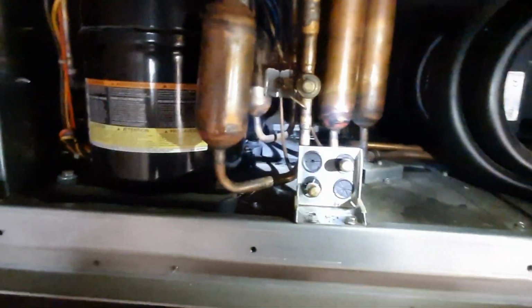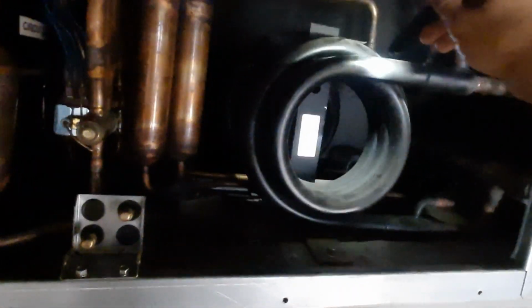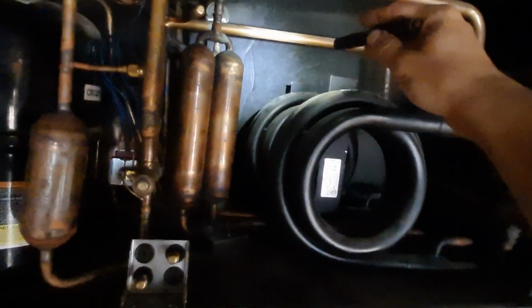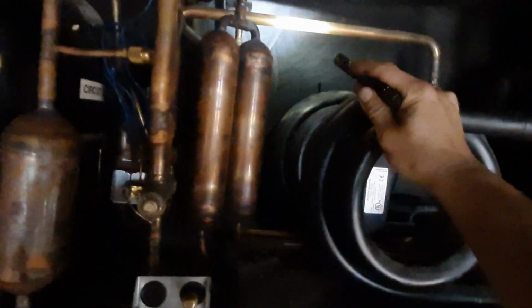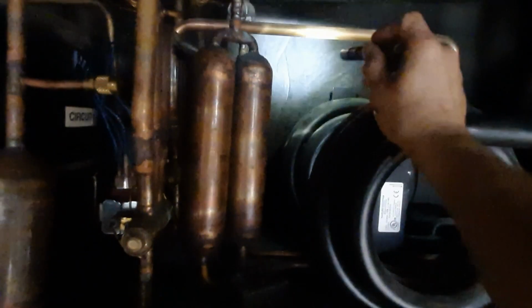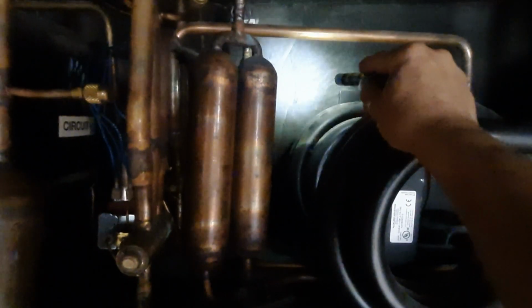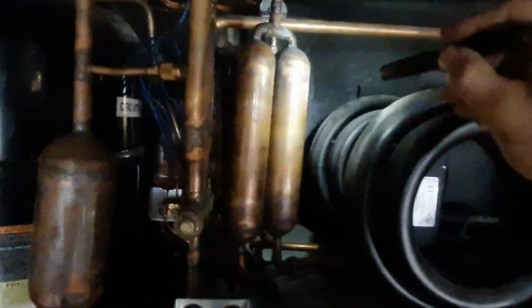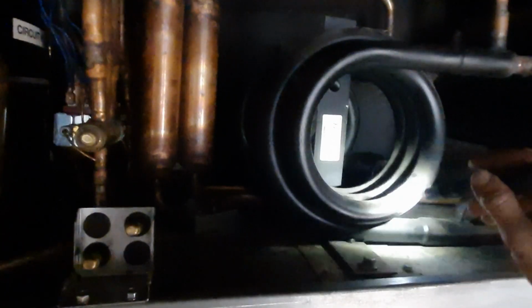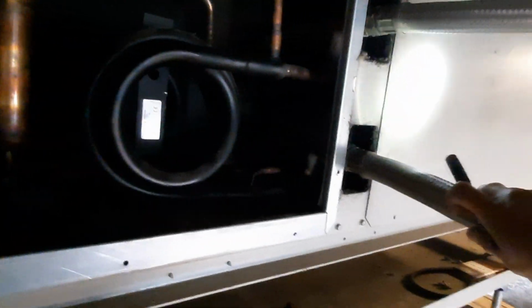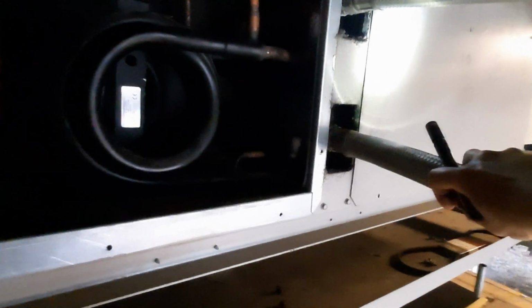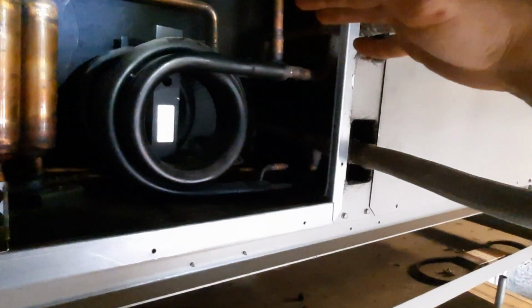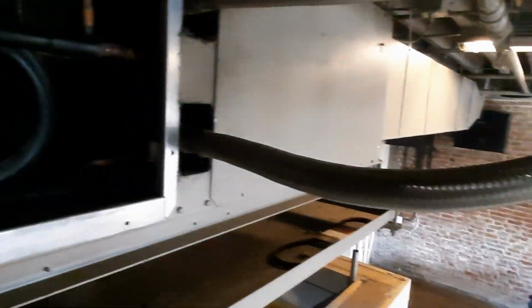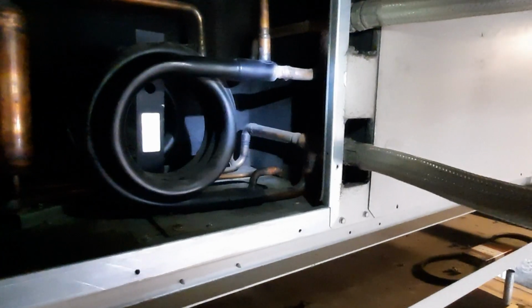When we reverse that cycle, our condenser coil becomes our evaporator coil, and our evaporator coil becomes our condenser coil. So we send hot gas through our now condenser coil, and we're able to heat the air. In that case, our condenser coil turns into our evaporator, and we actually will cool our water. So in cooling, we're heating our water up and going back to our water loop, and in heating, we're actually cooling this water down.